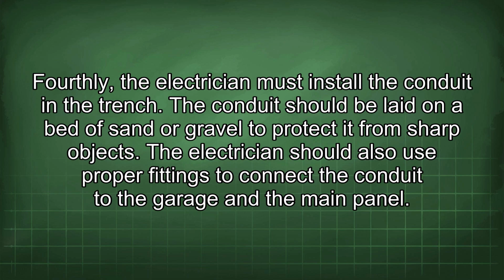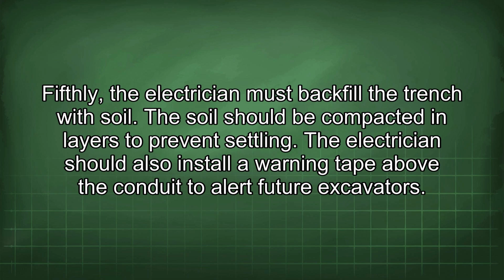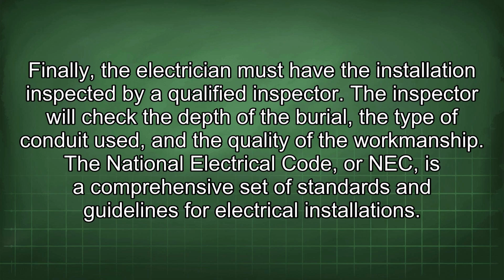Fourthly, the electrician must install the conduit in the trench. The conduit should be laid on a bed of sand or gravel to protect it from sharp objects. The electrician should also use proper fittings to connect the conduit to the garage and the main panel. Fifthly, the electrician must backfill the trench with soil. The soil should be compacted in layers to prevent settling. The electrician should also install a warning tape above the conduit to alert future excavators. Finally, the electrician must have the installation inspected by a qualified inspector. The inspector will check the depth of the burial, the type of conduit used, and the quality of the workmanship.